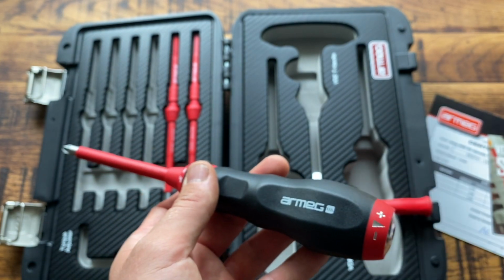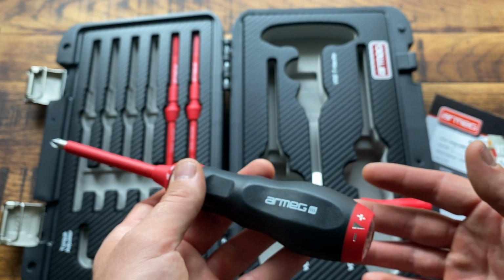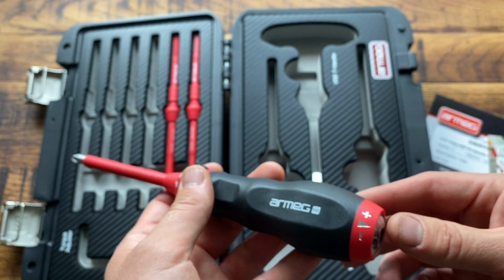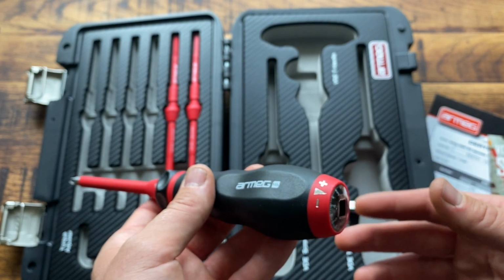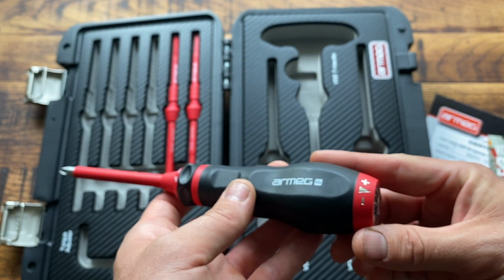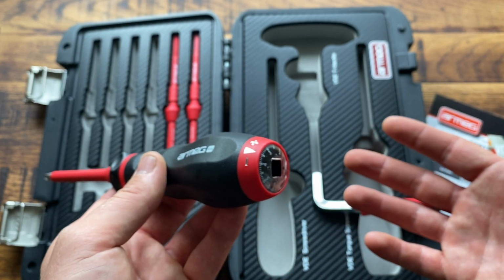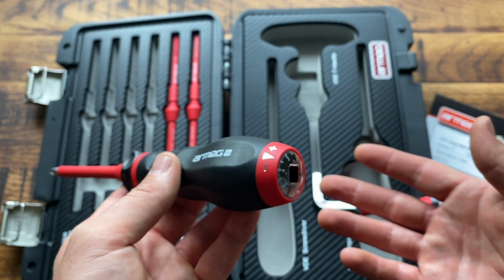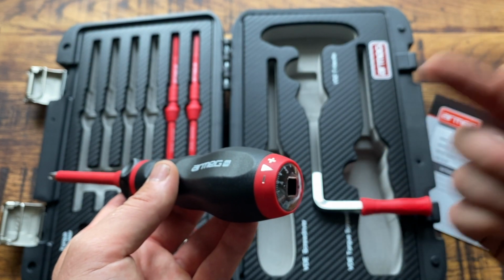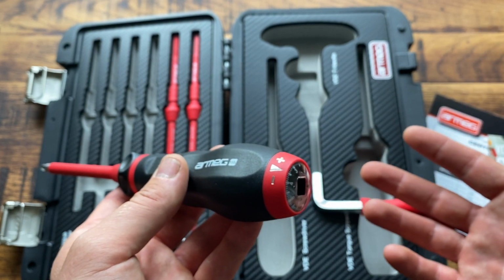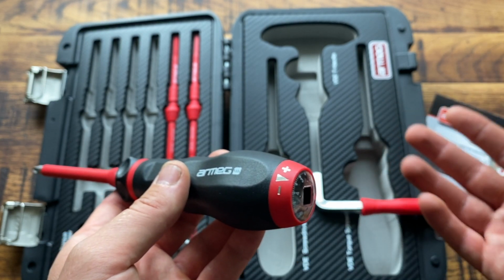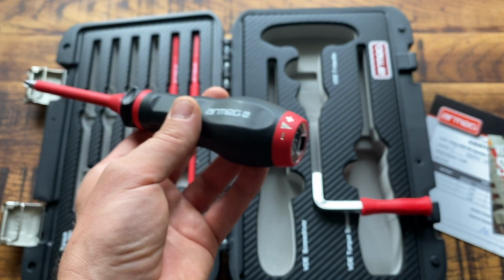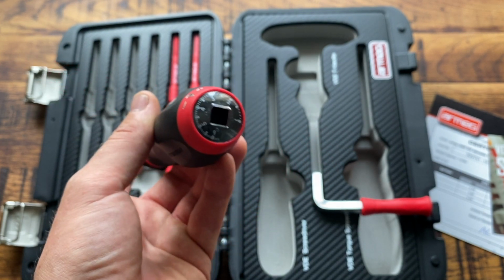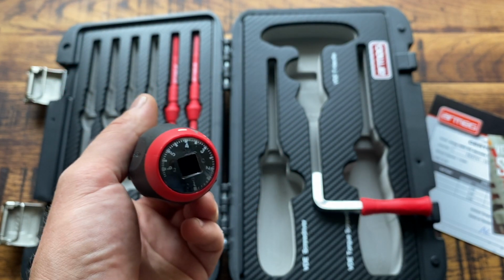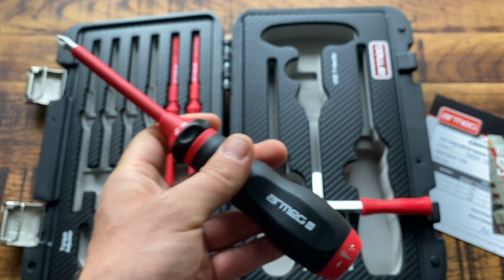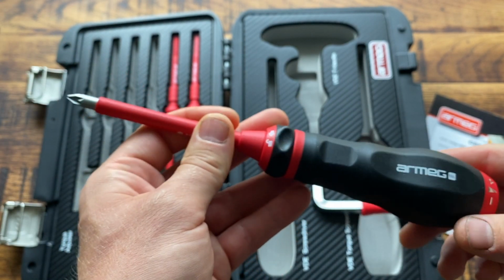For example, say you rock up at somebody's house and find they've got a Crabtree Starbreaker consumer unit, and you want to know what torque the outgoing terminals of the circuit breakers should be torqued up to. Obviously you're not going to have manufacturer's instructions lying around. So what you can do is simply Google the torque settings for that model, and usually you'll find somewhere on the internet a set of torque settings required by the manufacturer. In most cases you can find the torque settings you need.